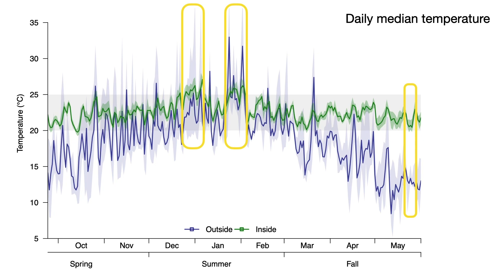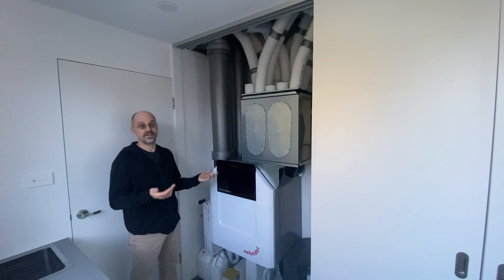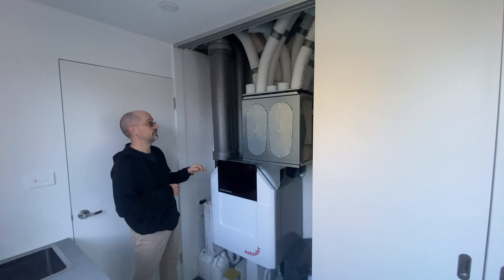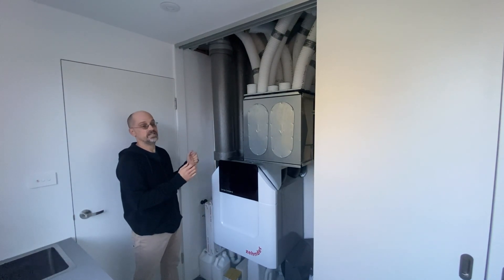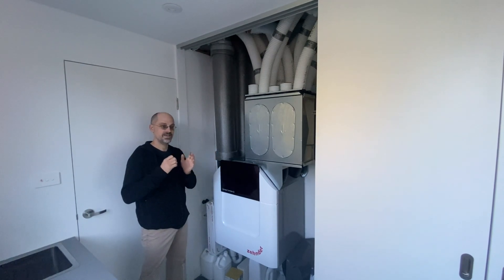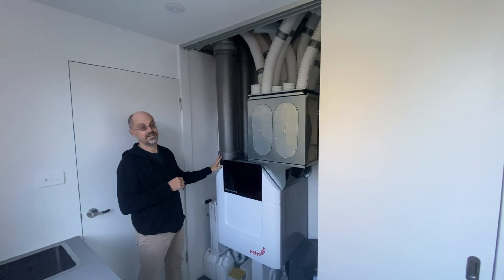There's been an occasional blip this winter with cool temperatures, during which time they have used the air conditioning. One of the defining characteristics of the passive house is that it's exceptionally airtight, which means that as occupants you constantly exhale carbon dioxide and moisture and need fresh air to breathe — and that has to be supplied somehow. In our house, this is the system that does that: two fans constantly pulling air in and pushing air out, and in that process it exchanges the heat between the air coming in and the air going out. So your house stays the temperature it is, and in summer you stay cool and in winter you stay warm, even though this is not a heater or an air conditioner.